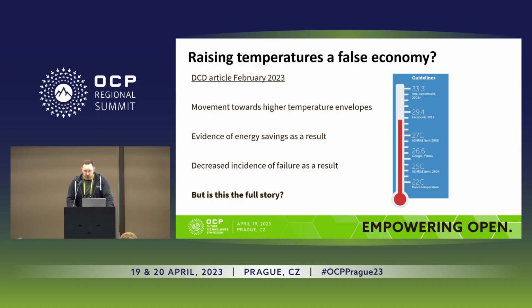What they found was there was basically no impact on failure rates as you raise temperatures, both to top end of ASHRAE allowable at 27 degrees and up to 30 and 33 degrees as well. There was no increased failure rates, and there was no lack of redundancy caused by that.